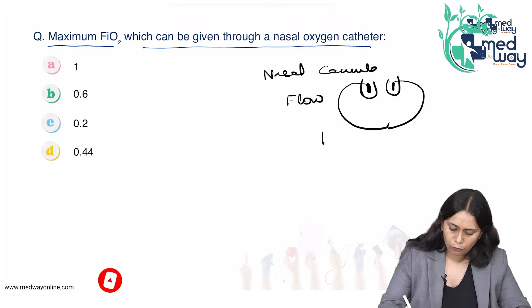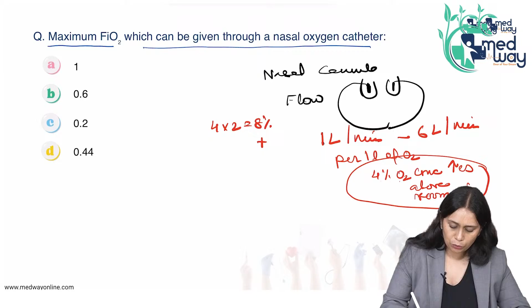How much flow do we give? We can start from 1 liter per minute and go till 6 liter per minute. Per 1 liter of oxygen we are giving through the oxygen piping, oxygen concentration increases by 4% above room air. So if I am giving my patient oxygen at 2 liter per minute, 4 into 2 is 8%, plus 21% the room air oxygen concentration. So the patient is getting 29% oxygen.